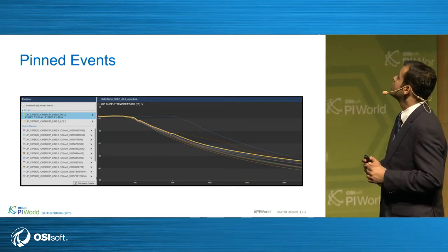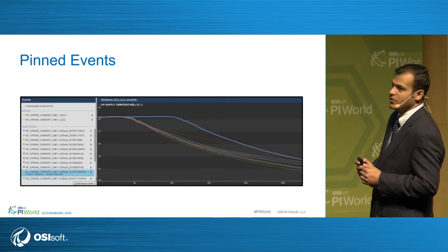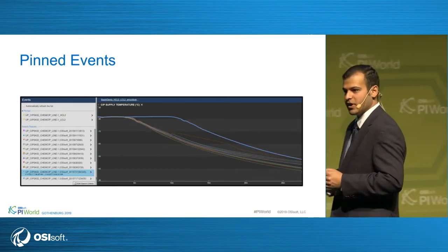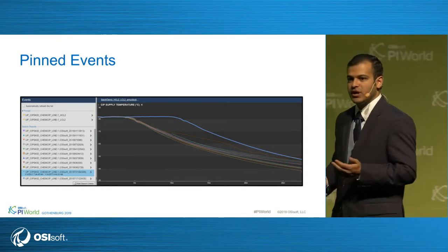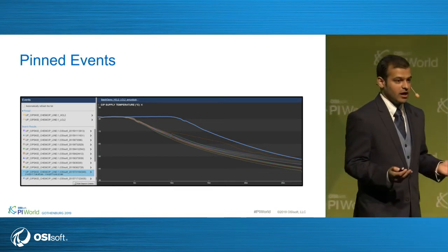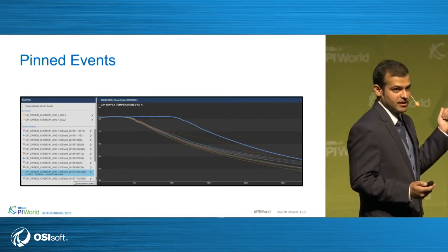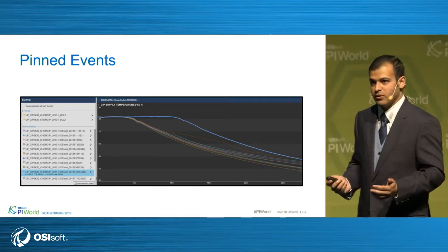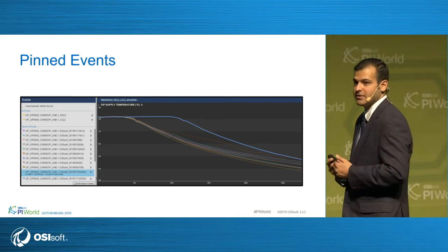I'm seeing if something deviated from that. Clearly, the blue one over there deviated over that. So my upper and lower limits are here, but if I look at the event frame of interest to me, it's showing some deviation. And that's where, especially if I'm doing batch processes, I could catch abnormalities, anomalies right on time. I could see where something went wrong, and I could save a lot of loss before it goes and feeds the entire batch.